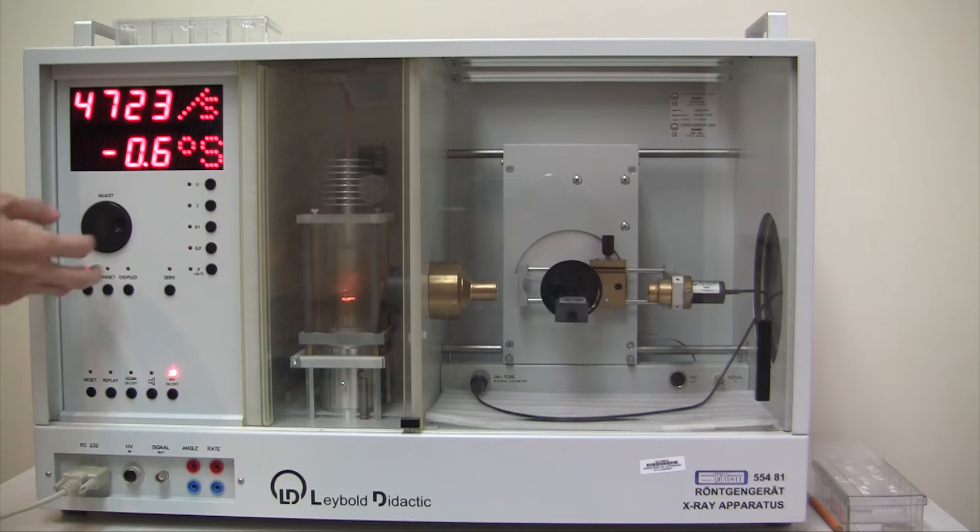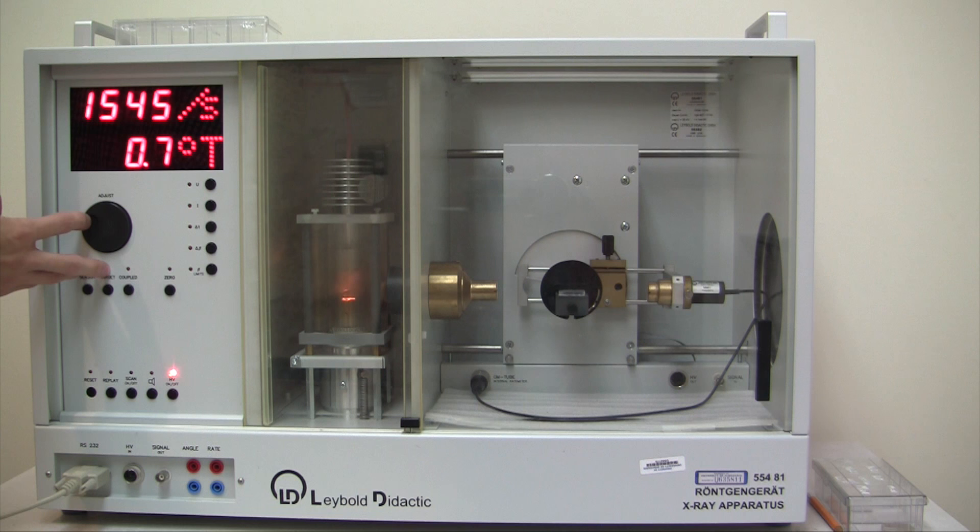Rotate the sensor manually until the X-ray count rate is maximized. Turn off the high voltage, open the sliding window and raise the crystal until it is snug against the stop. Turn on the high voltage and rotate the target until the count rate is at maximum. If the alignment is good, then this count rate should be about half of the original count rate without crystal in place.